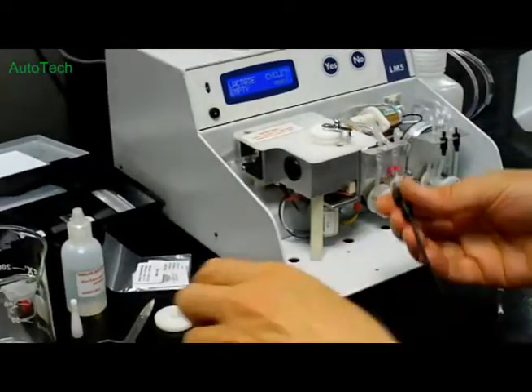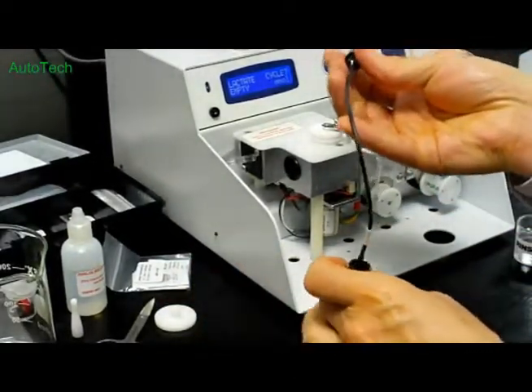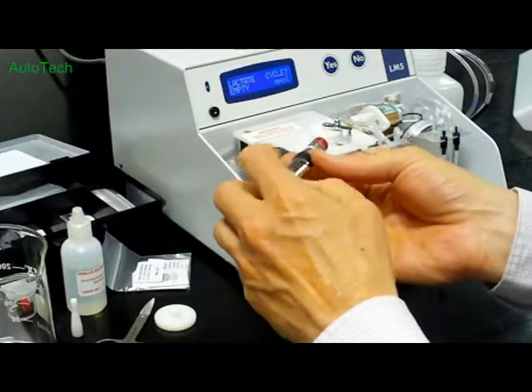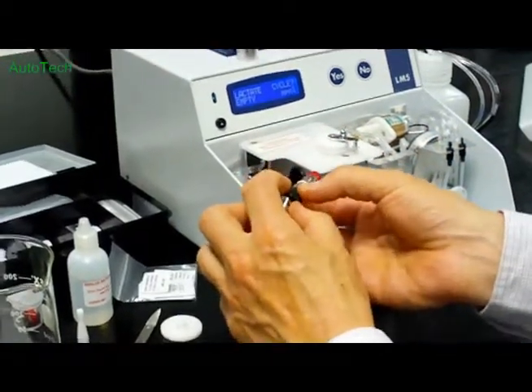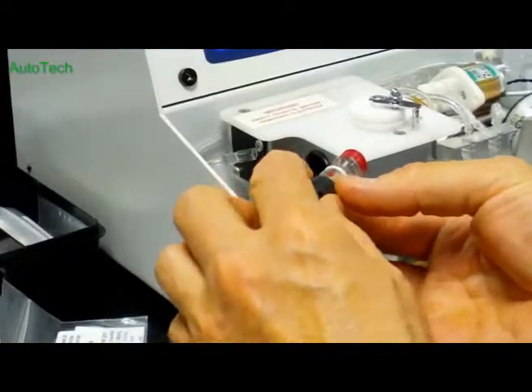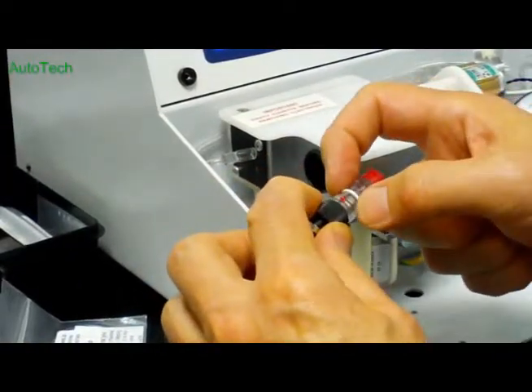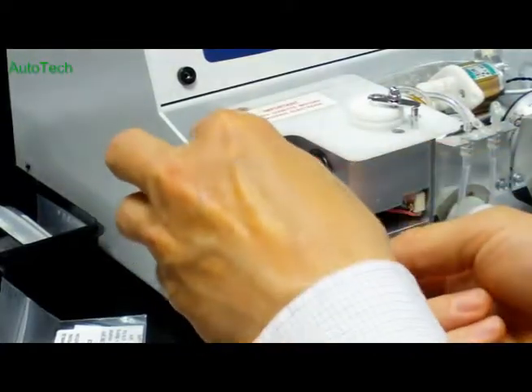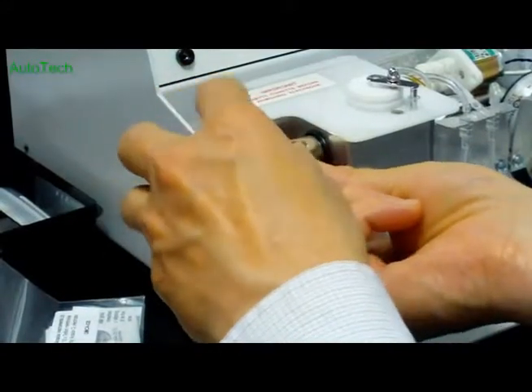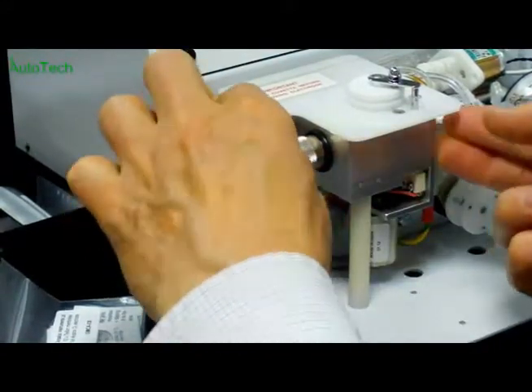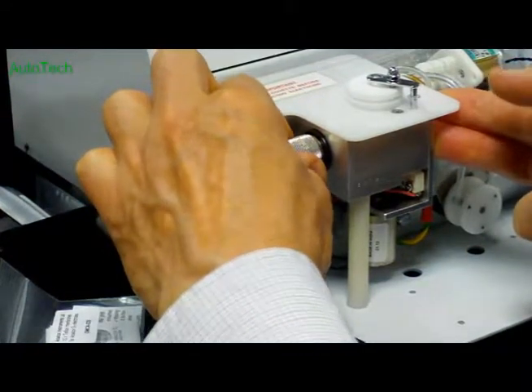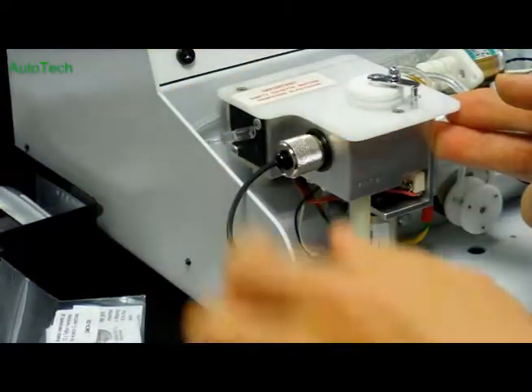So now we're going to reinsert the electrode. And it's always good practice to have the red dot uppermost. And just double check the O-ring is in place over the bleed hole. And so sliding it into the electrode chamber, just locate the bayonet and turning clockwise you'll feel a gentle click to confirm that the bayonet is in place.